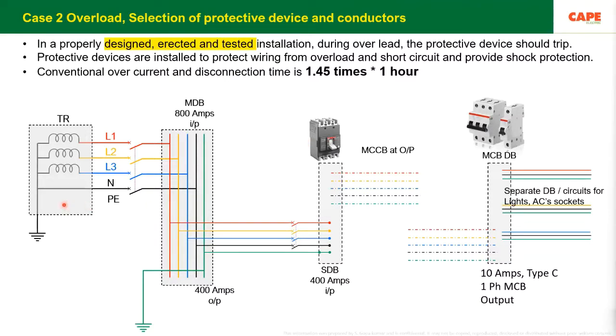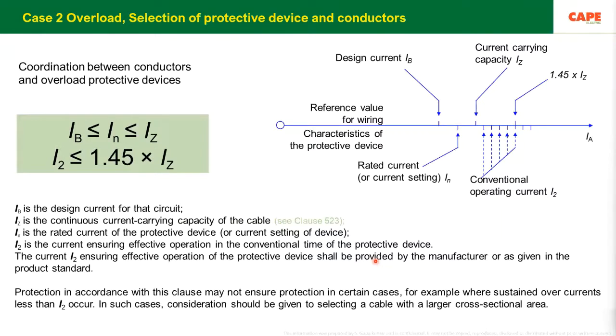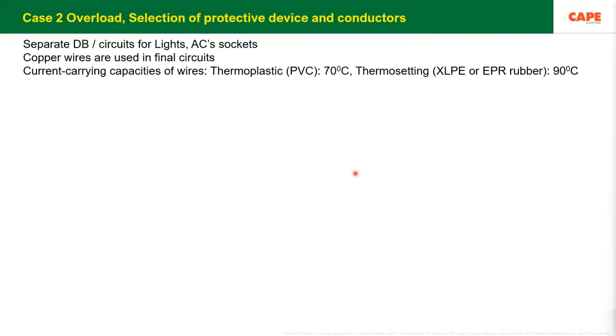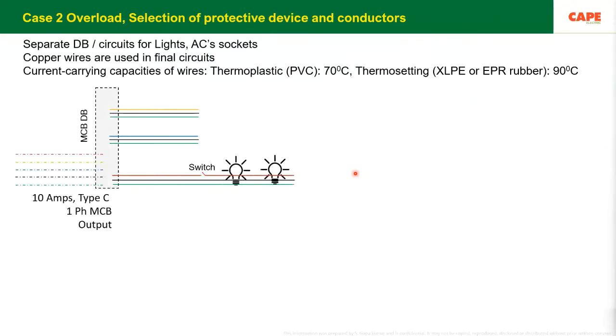So the challenge here is, the protective devices must be rated appropriately, selected appropriately for that particular application, depending upon the size of the conductors, depending upon the disconnection time, and so on. You can see the selection measures in the standard IS 732 in clause number 4.2 and 4.3. There are different measures to select it. I am not going into detail of the entire measures. Basically, these protective devices, such as MCBs, MCCBs, are supposed to protect the wiring. It is not supposed to protect an apparatus. It is supposed to protect the wiring from an overload. That means once the current is more than the designed current, then of course the device is supposed to trip.